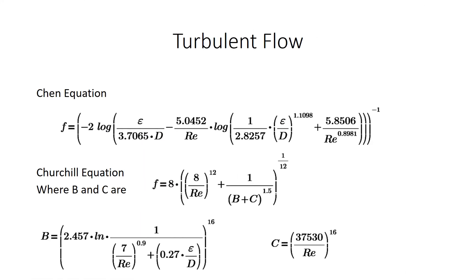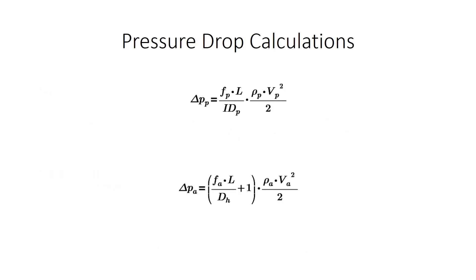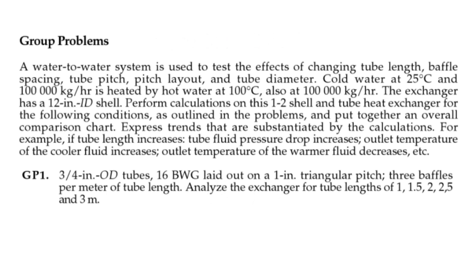For the turbulent flow, both inside the tubes and in the annulus region, we can use the Chen equation or Churchill's equations. They both result in the same friction factor. After we calculate the friction factors for the annulus region and for the tube region, we will use the major loss equations from modified Bernoulli's to calculate the delta P.